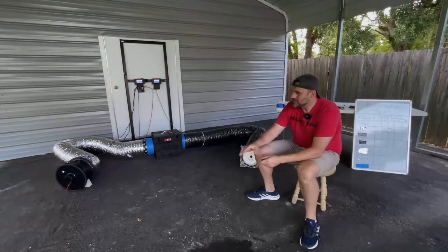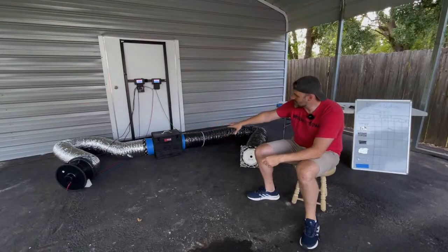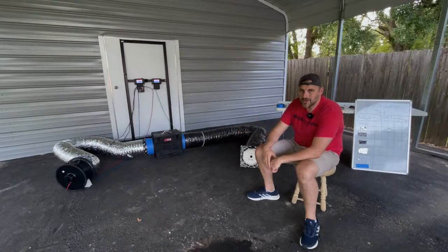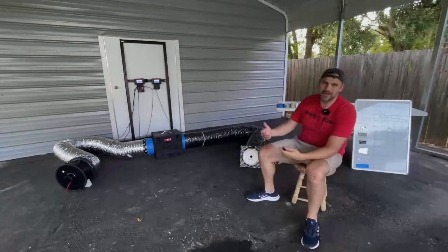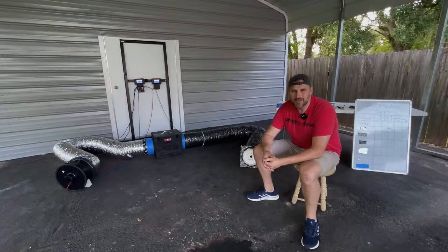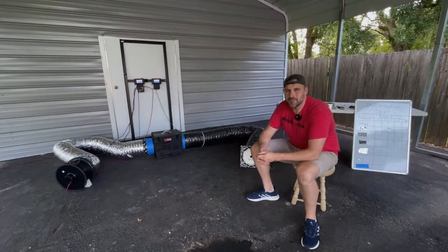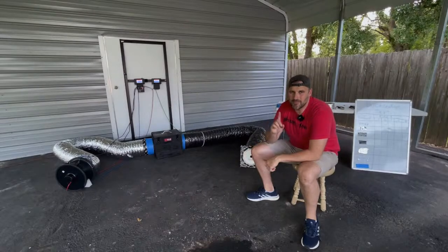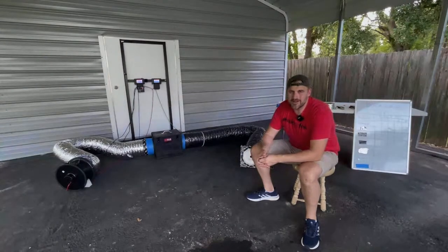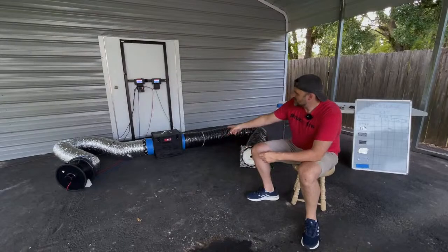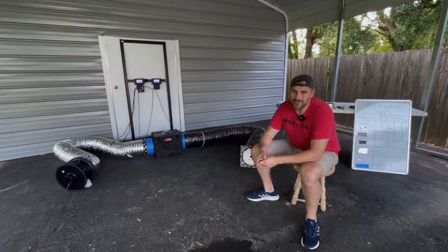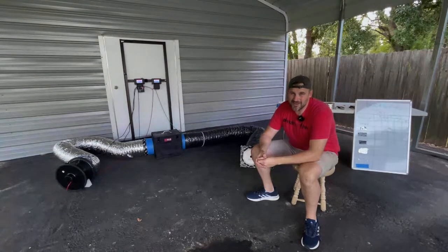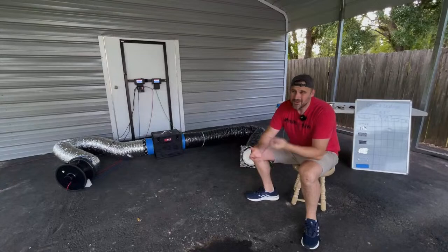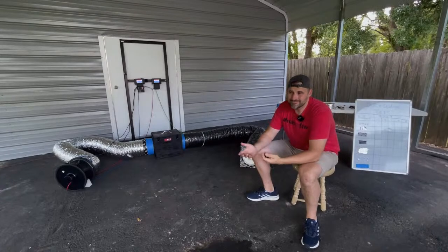Here's what's happening. We are gonna determine the duct leakage when you connect flex to a collar. We're gonna use the various tapes and panduit strap that we normally use in the trade. On this board right here, we're gonna measure that leakage, at 0.1 all the way up to 0.5 inches of water column. Not only are we gonna measure it, we're gonna smoke it out and see what that leakage looks like. We're gonna determine, is it significant if you just do a panduit strap, or is it not significant? We're gonna find out.